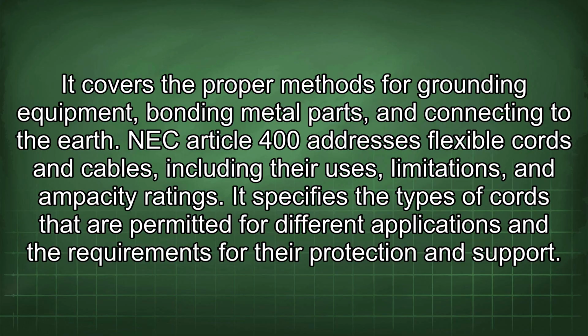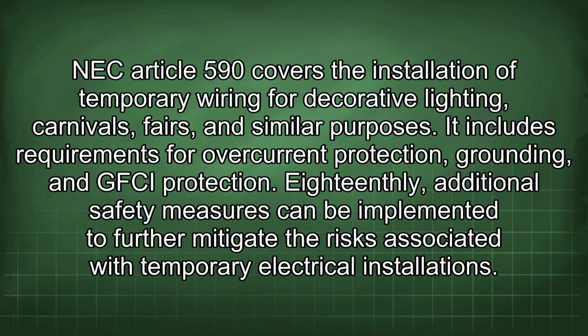NEC Article 400 addresses flexible cords and cables, including their uses, limitations, and ampacity ratings. It specifies the types of cords that are permitted for different applications and the requirements for their protection and support. NEC Article 590 covers the installation of temporary wiring for decorative lighting, carnivals, fairs, and similar purposes. It includes requirements for overcurrent protection, grounding, and GFCI protection.